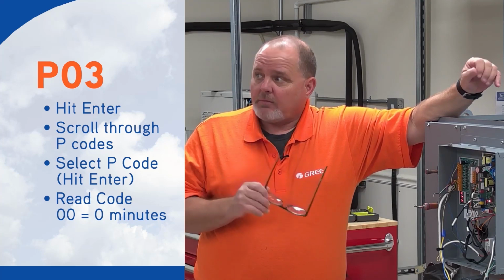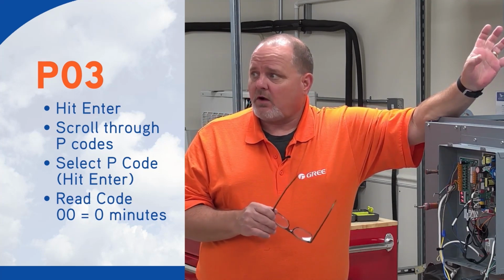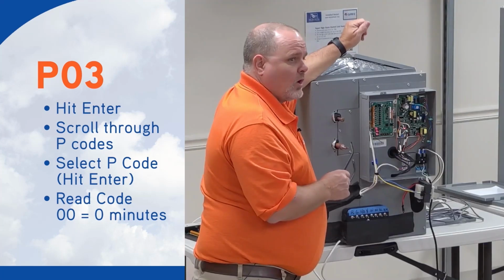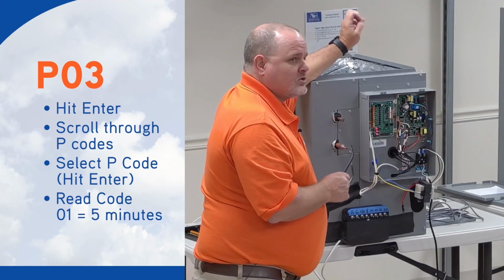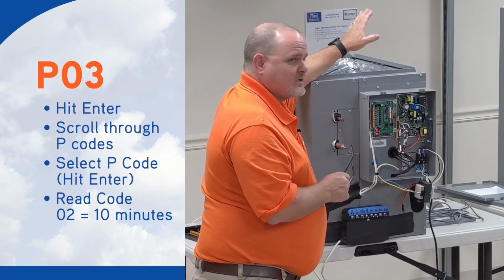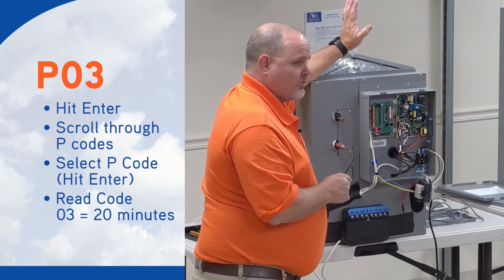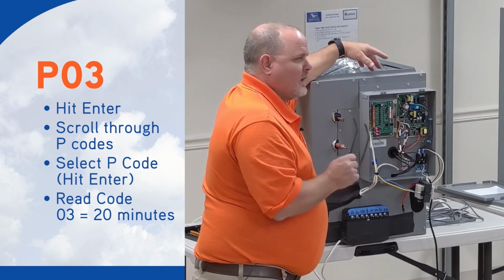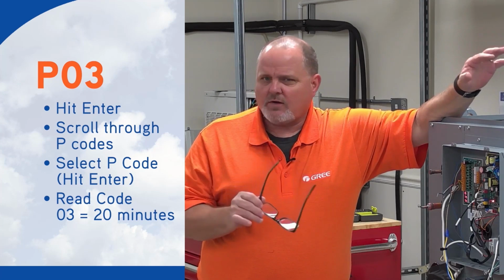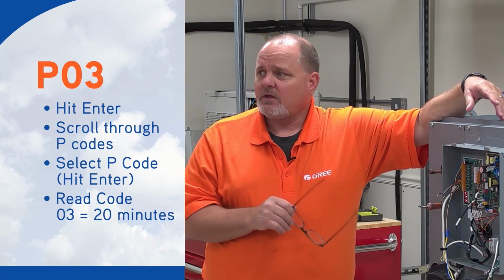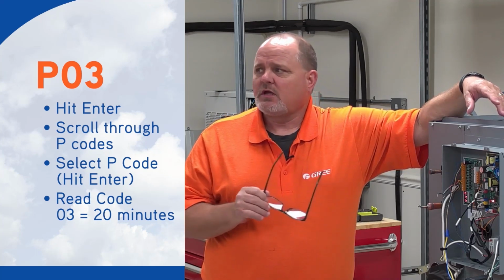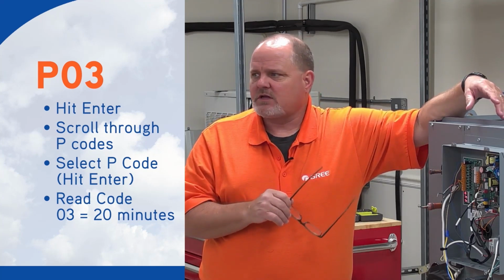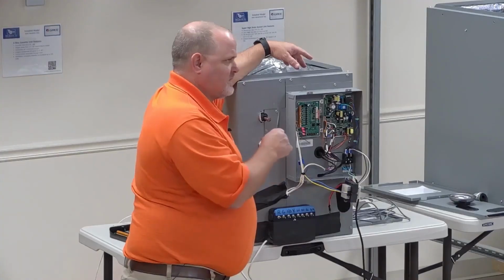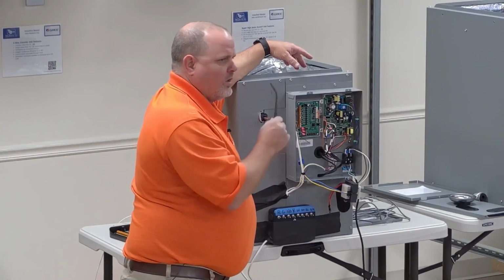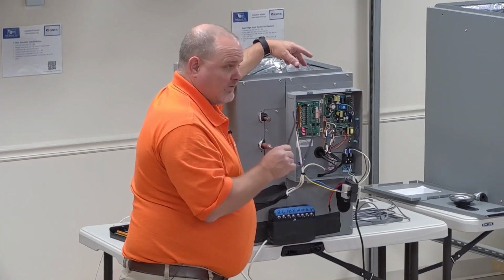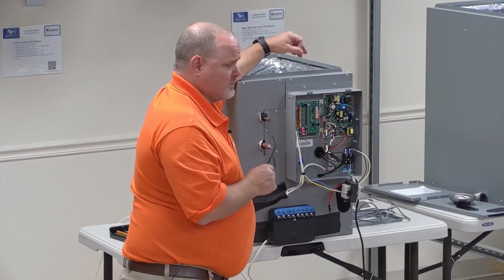So I would be setting it probably at 00, so I have a 0 minute off delay. But 01, I believe, is going to be 5 minutes. 02, I believe, is going to be 10 minutes. And 03, I believe, is going to be 20 minutes. I'm a little unsure on that because, again, the 24-volt adapters are production. And the way they had it set up on the previous adapter, we changed that a little bit in the design setup of doing the dual fuel coil and for the 24-volt adapter. And I believe that's what we expect that we wanted the time delays to be.